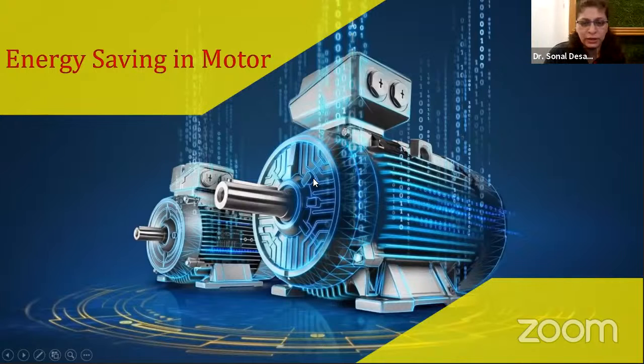So friends, in the second part, I'll be talking about energy saving in motor. Motor is always the backbone of a pump, not only pump, many other devices. Whenever there is a fan, whenever there is a compressor, whenever there is any driven rotary machine, there is a motor used. And the problem with the motor is we normally don't buy a motor from the industry. We either buy a pump, a compressor, or a fan. So what is the motor type? Whether it is an energy efficient motor, what are the performance parameters of the motor, that is not asked.